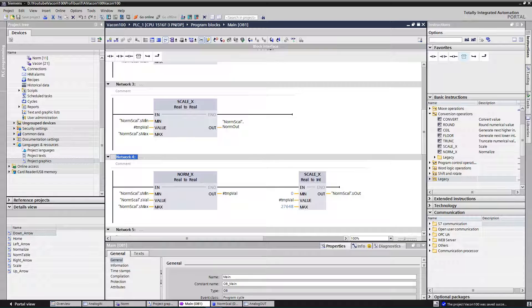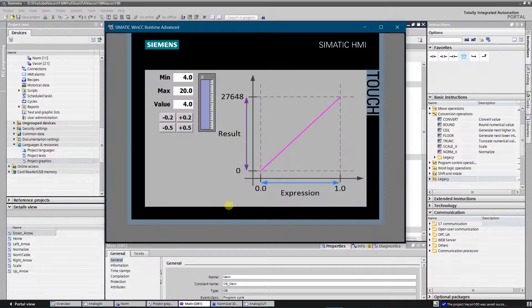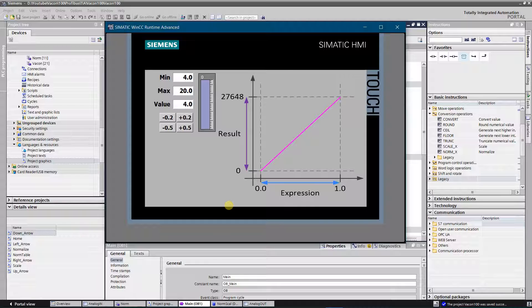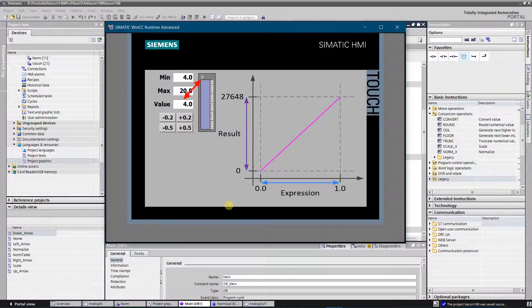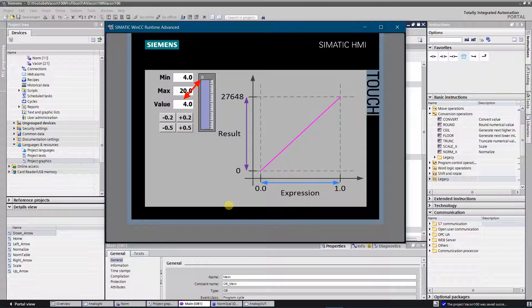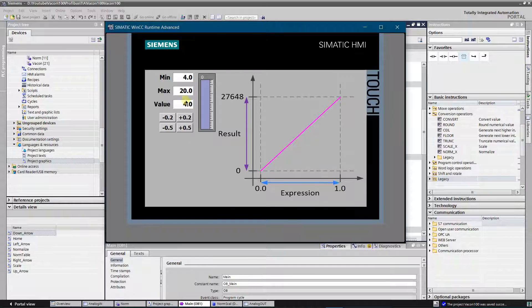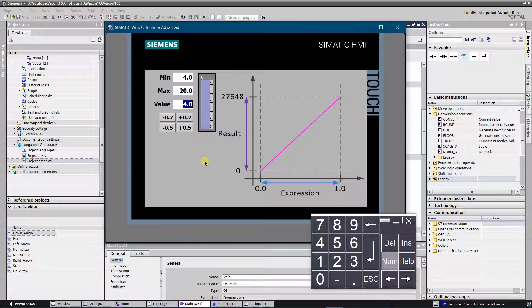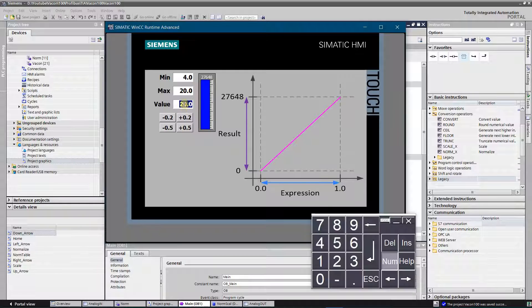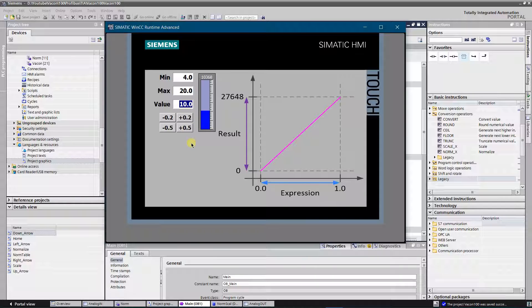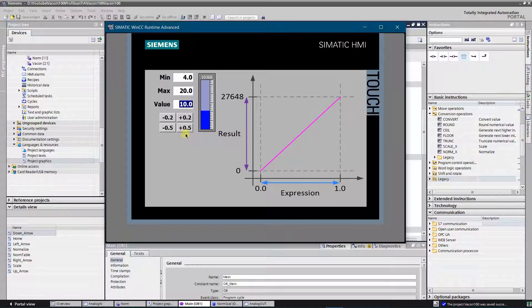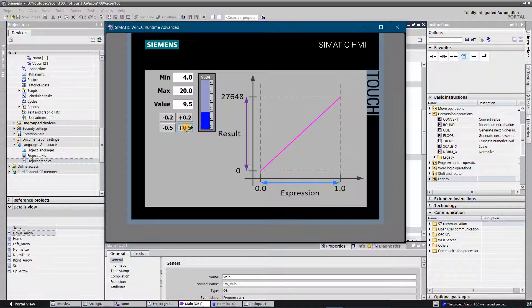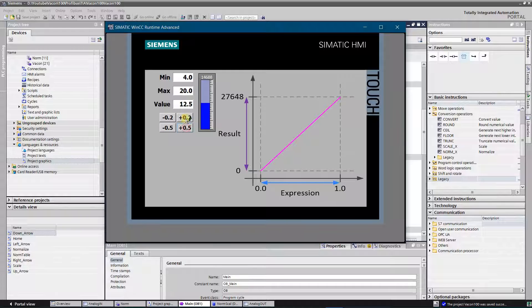All is done, let's try our program. By default my NORM_X limits are 4 to 20. As you can see, the value of analog output is 0 while setpoint is 4. Let's make it 20. Now the value of the analog output is 27,648. All the other setpoints are within scale of 0 to 27,648.